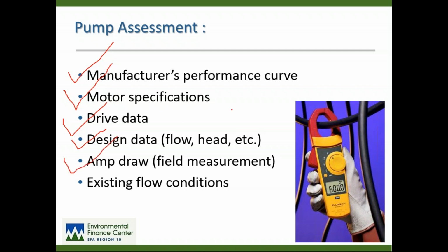If you are qualified and trained to do what that person in the photo is doing and actually open up your motor control center with an amp probe, that's the instrument that person has in their hands, and take running amp readings, that's one of the things we do when we come out and do an energy audit. If you're not trained or you're not a certified electrician, I wouldn't recommend doing that because it can be very dangerous, but some of us are trained. And then you look at your existing flow conditions and whether those conditions are going to be adequate now. Will they be adequate in the future as your system changes, as your population goes up?